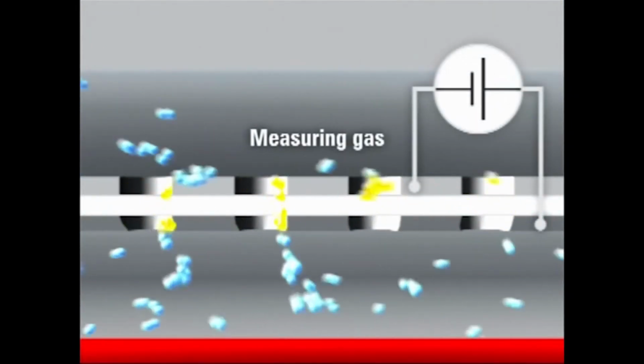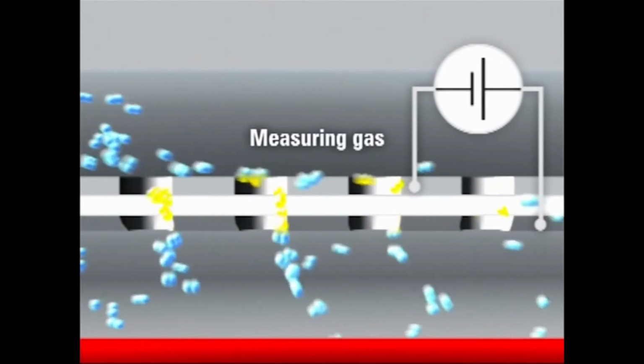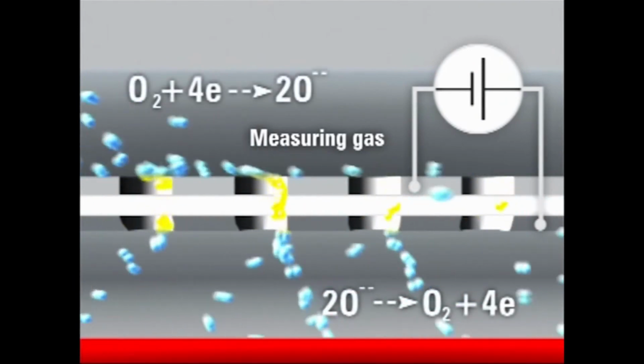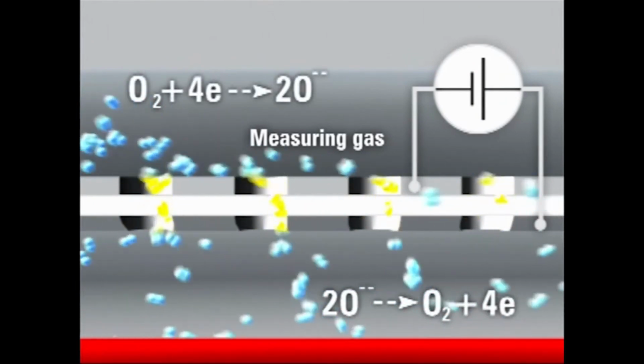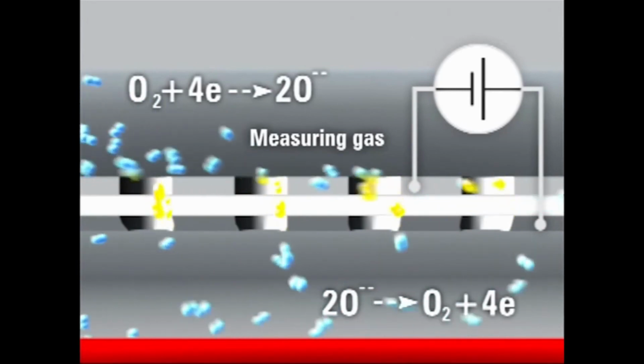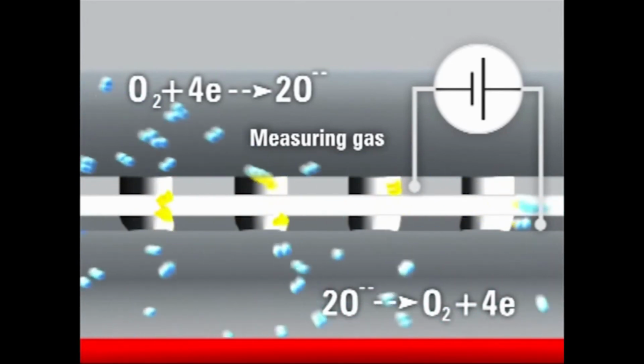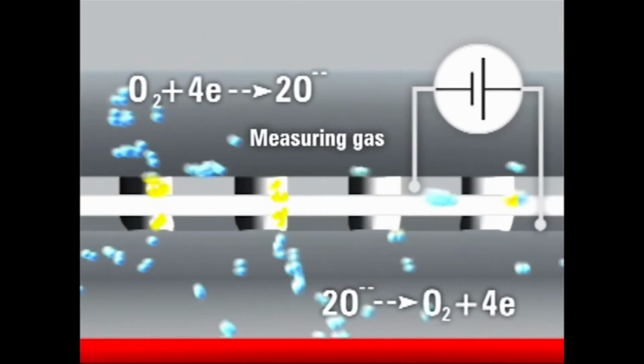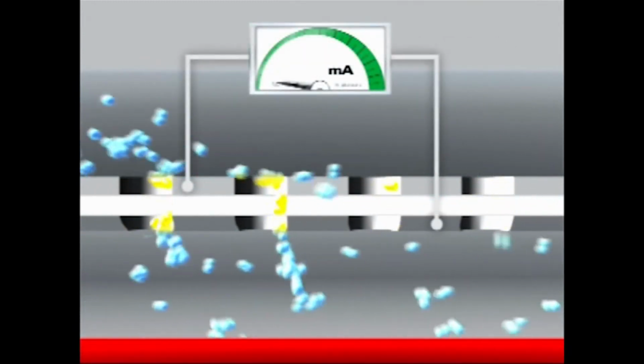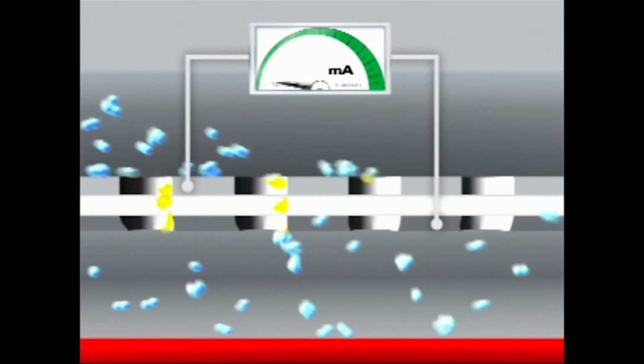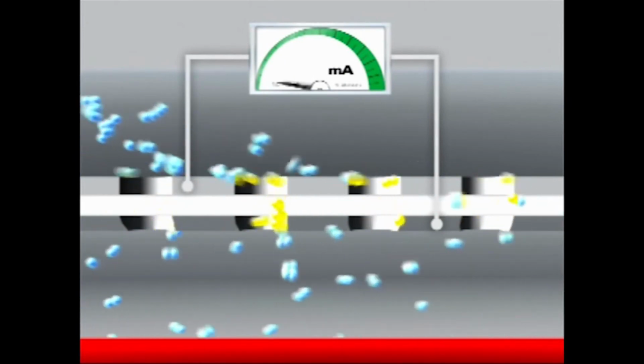Impressing a voltage between the two electrodes of the zirconia measurement cell forces a current to flow. 4 electrons flow per oxygen molecule. During constant gas flow, the current level increases, and hence also the measured signal, in linear relation to the oxygen content in the measuring gas. In other words, 0% oxygen means that there is no flow of current.